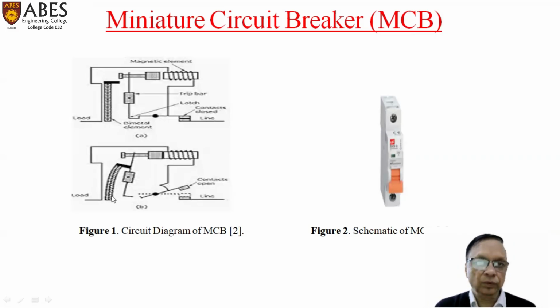But in case of a short circuit condition, because the current is of a high magnitude and requires instant tripping of the breaker, here we have a plunger. This plunger will be attracted to the magnetic element. Under short circuit condition, magnetic field poles will be defined and attraction will take place. Due to this attraction, as we see in the second diagram, the latch will be dislocated from the contacts. Under this condition, the contacts will open.